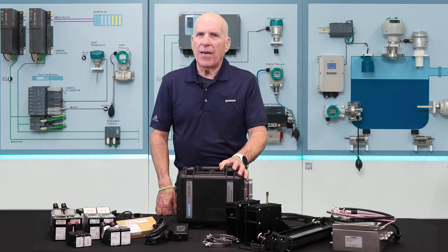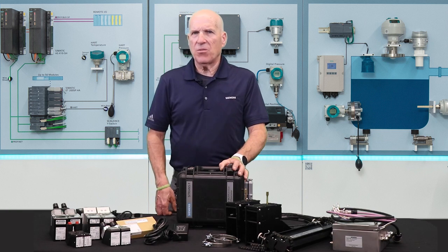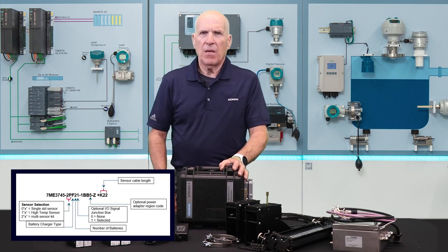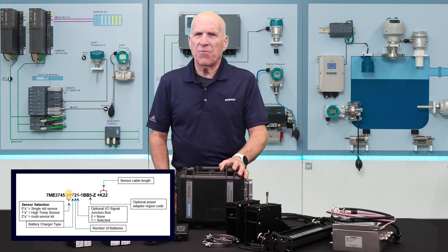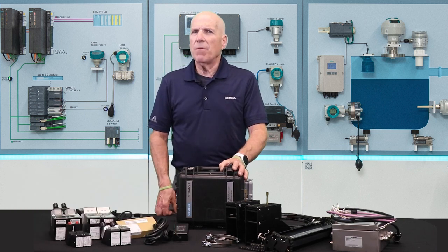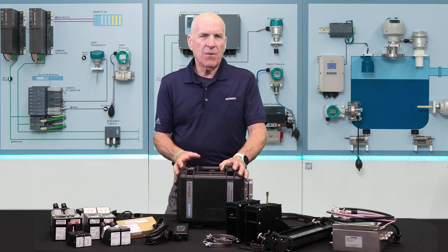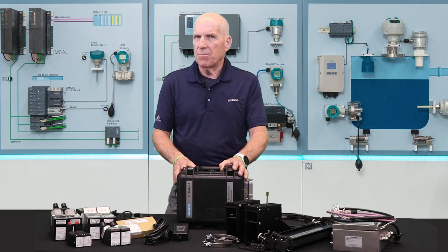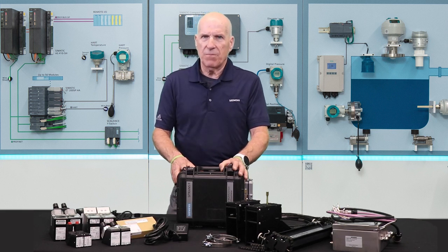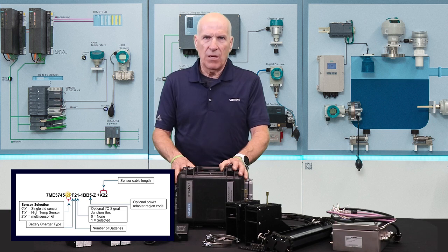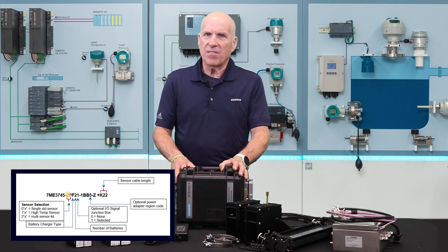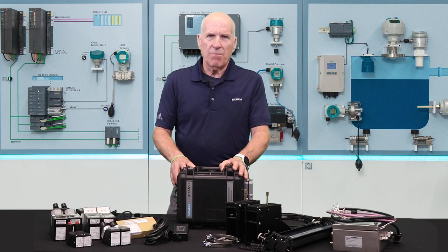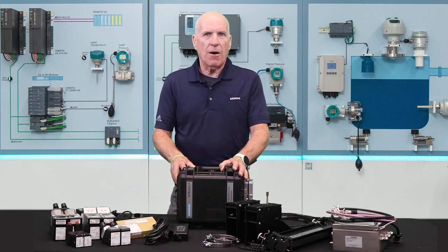Along with your FS290 transmitter, you'll receive one or more sets of FS200 flow sensors and mounting hardware. Characters 8 and 9 of the system part number define what sensor size and type you'll receive and what mounting hardware. Since this is a portable meter, it can be used on a wide range of pipe sizes and types. To facilitate such usage, a variety of check meter kits are offered that contain multiple sensor sizes. Therefore, instead of a single set of sensors, you may receive one of these check meter kits. They are indicated by a 2 in the sensor code, such as seen on this meter, which indicates sensor code 2P. With many possible sensor and mounting options, let's take a closer look at what they are.